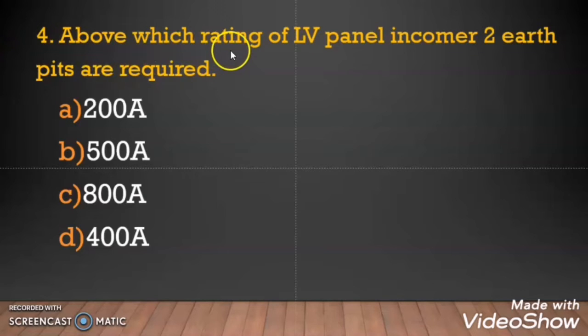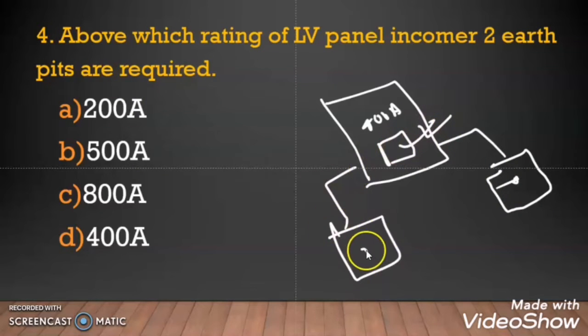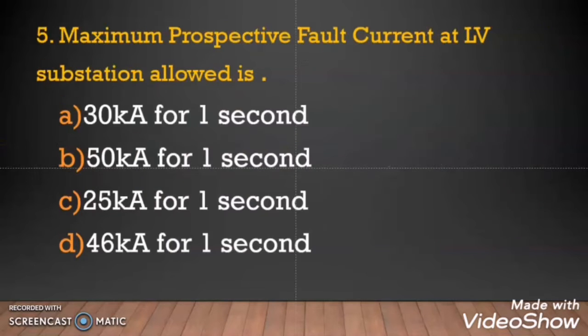Question 4: Above which rating of LV panel incomer are 2 earth pits required? As per ADDC regulation, suppose you have one LV panel and the breaker rating is 400 ampere — you need an earthing system for that panel. The answer is 500 ampere or above. For LV panel incomer rated 500 ampere or above, 2 separate earth pits are required. So the answer is option B, 500 ampere or above.